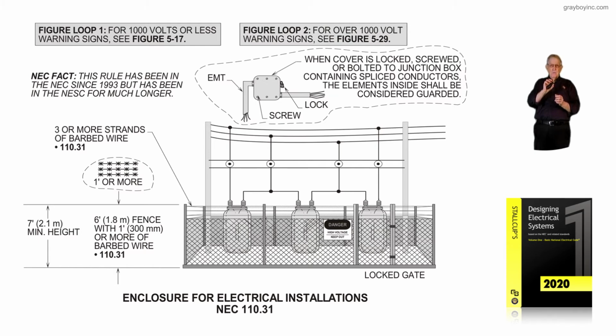They also own this substation. So you could use 3 strands of barbed wire and get it up to 7 foot. Now, look at the NEC fact. This rule has only been in the NEC since 1993, but it's been in the National Electrical Safety Code for a long time. Why? Because usually a substation was owned by the utility. Not so anymore. Many facilities own their own substation.